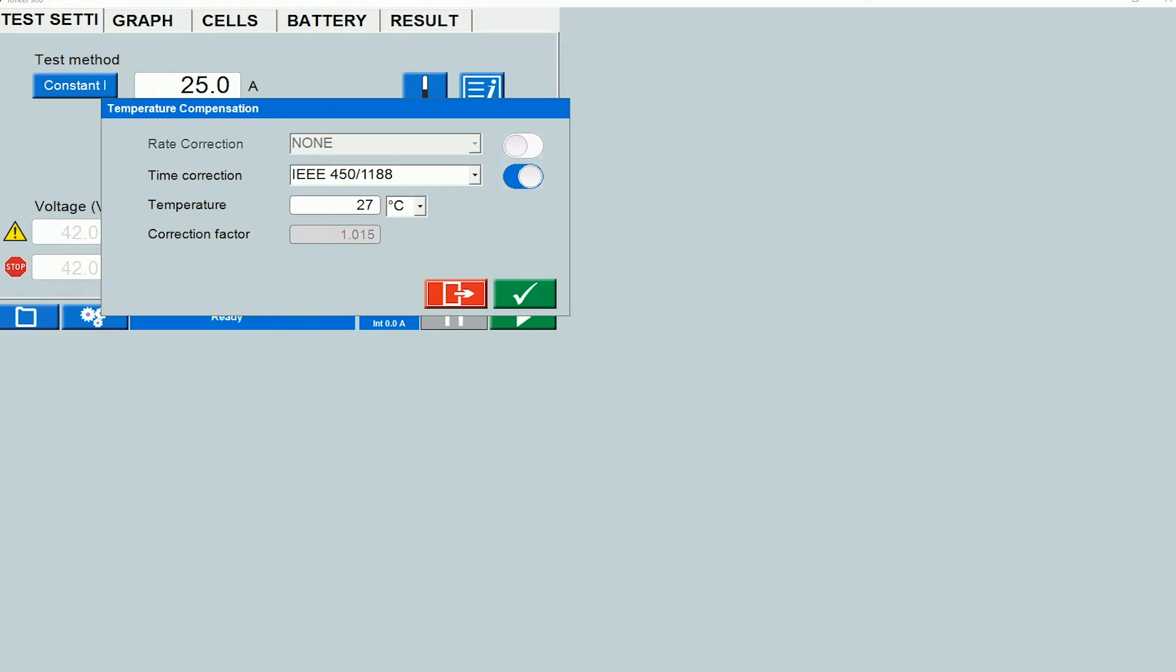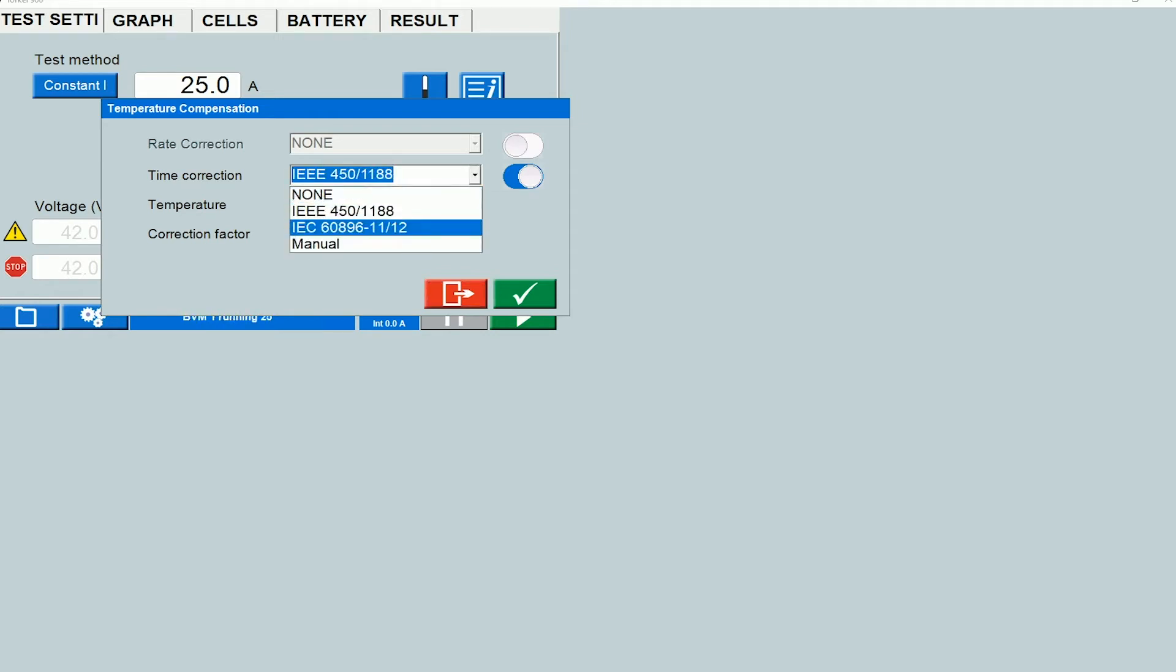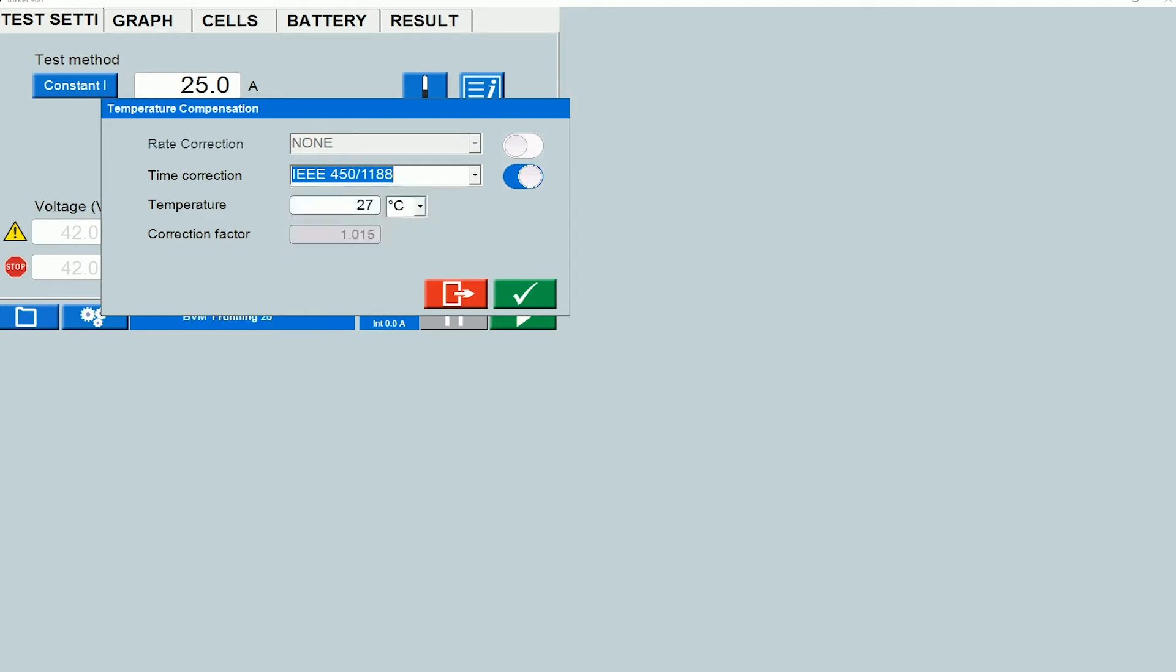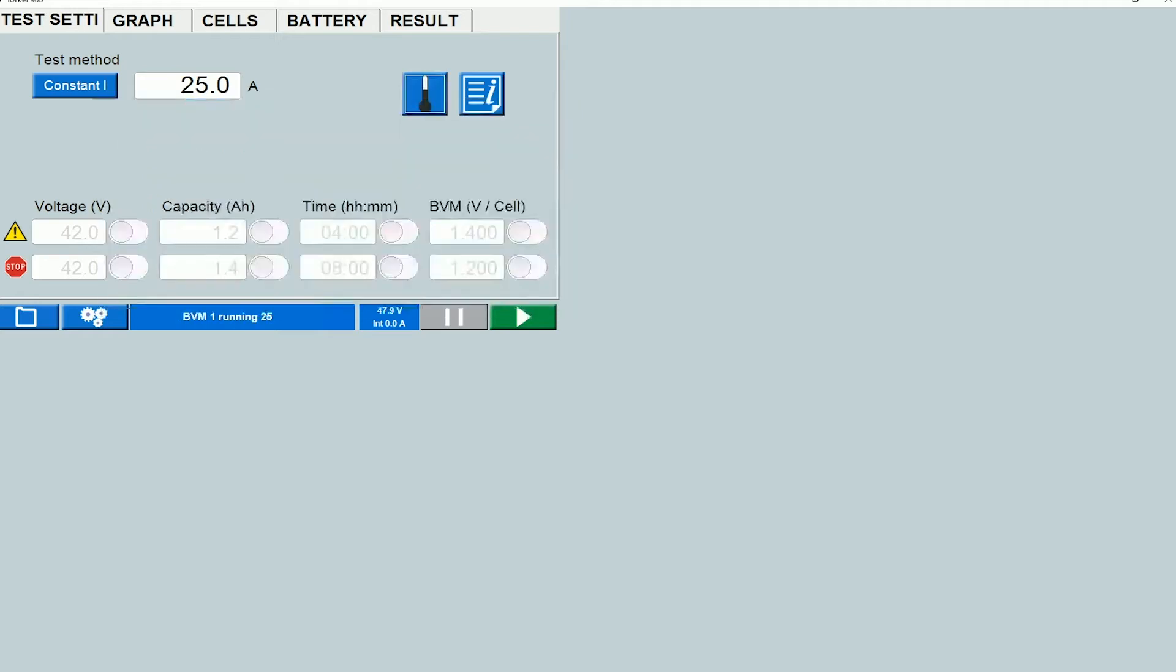If I click on the drop-down I can see the additional options. For here in the states you would select the IEEE option if you are testing a lead acid battery because these standards are meant for maintenance and testing on lead acid batteries. 450 is for flooded lead acid. 1188 is for sealed lead acid. The temperature of 27 Celsius is selected and you can see that the correction factor populates over here based on the values that are provided in the standards. Click on the check mark to exit the window.